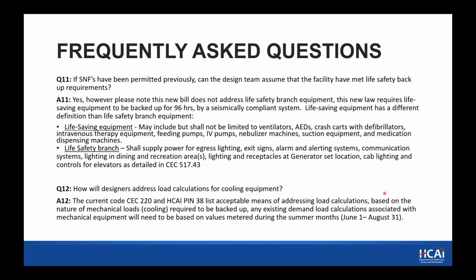How will designers address load calculations for cooling equipment? The current code, CEC 220 and HCAI PIN 38, list acceptable means of addressing load calculations based on the nature of mechanical loads, which is cooling, required to be backed up. Any existing demand load calculations associated with the mechanical equipment will need to be based on values metered during the summer months. We're looking at the cooling loads. We need to get a good representation of when they're in use. So that would need to be measured minimum of 30 days between June 1 and August 31st. Next slide.